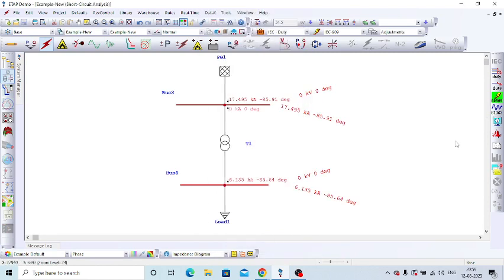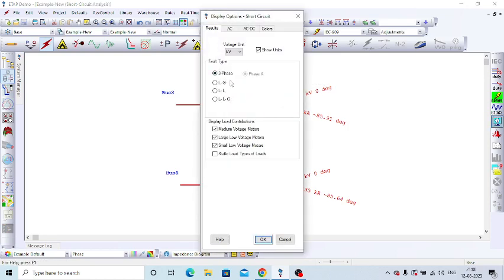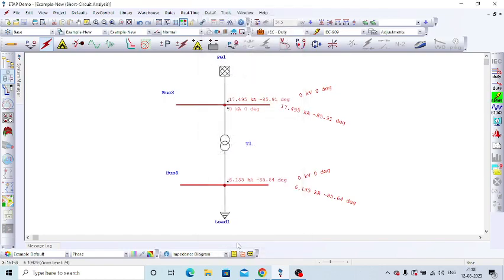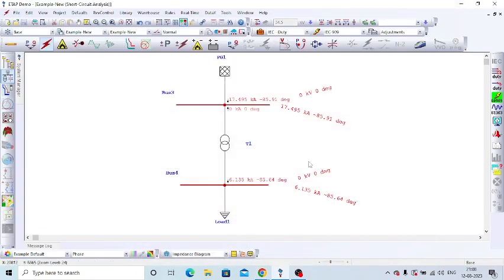Okay, so in most of the places we need to check all the types of faults for any selection of the circuit breaker. But in most of the cases, the three-phase fault current is normally higher than all other types of fault current. Suppose if you are calculating the three-phase magnitude fault current, that value is high, so other values are less. So the three-phase fault current is considered for the circuit breaker or other equipment selections. So in this single line diagram, we just saw how we can do the fault current study for the typical two bus system.